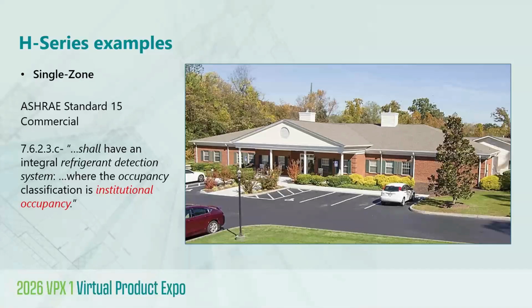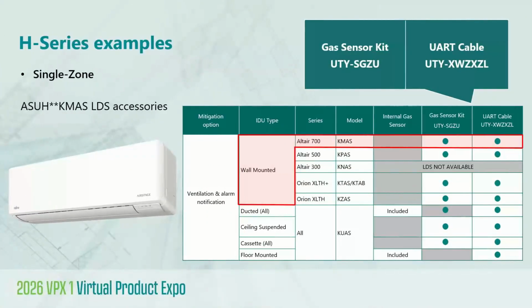Using that as a given, let's say that each apartment is going to require 9,000 BTU, let's just say an ASUH 09KM, that's part of the Altair family of wall-mounted units. Now, as Kushala discussed, all current production wall-mounted units will require a firmware update to be LDS compatible. So again, when you want that gas sensor to be able to communicate with the indoor unit, we have to do an indoor unit firmware update. The table excerpt that you see from our application bulletin shows that we only need to add the gas sensor kit and the UART cable to initiate circulation.